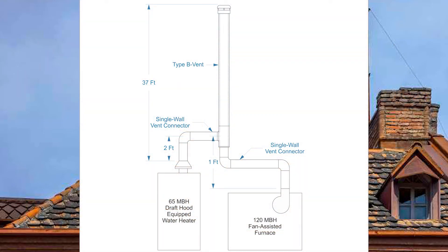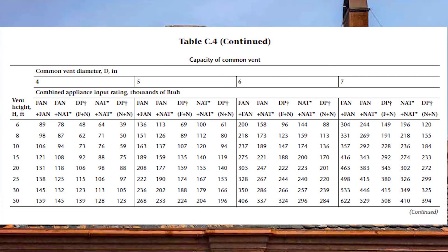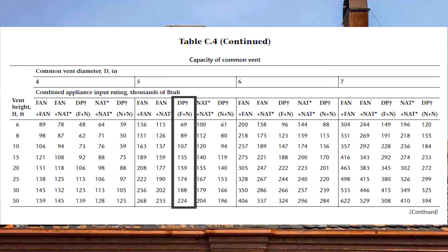Now let's size the common vent. Total BTU load is 120 MBH plus 65 MBH equals 185 MBH. Even though vent height is 37 feet and falls between table values, looking at a 4-inch common vent under DPF plus N: at 30 foot it's only good to 123 and at 50 foot only to 139, so 4 inch won't work. Moving to 5 inch: at 30 foot it's good to 188 and at 50 foot to 224 — that means no interpolation is needed at all. The common vent will be 5 inch.